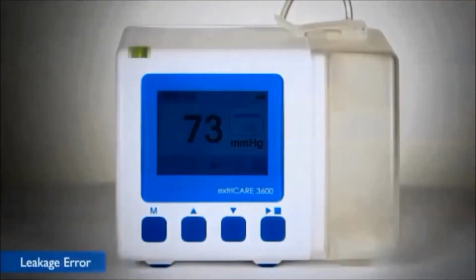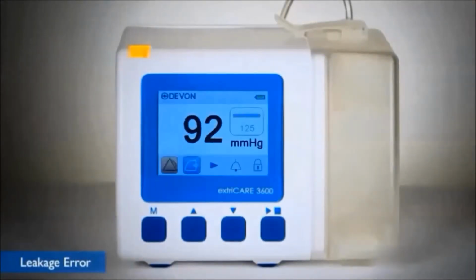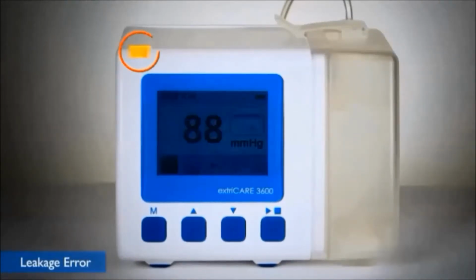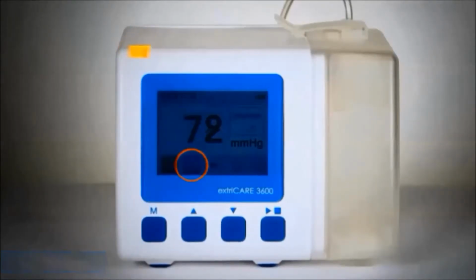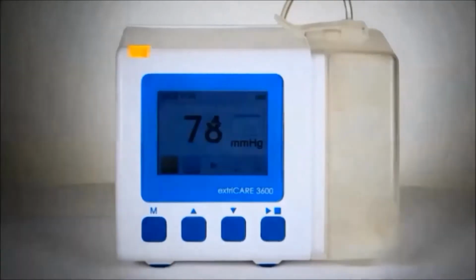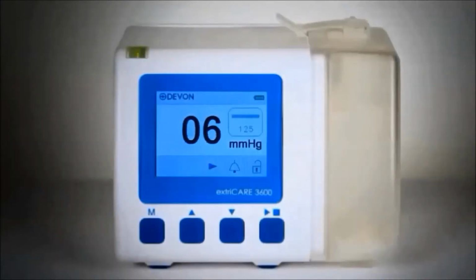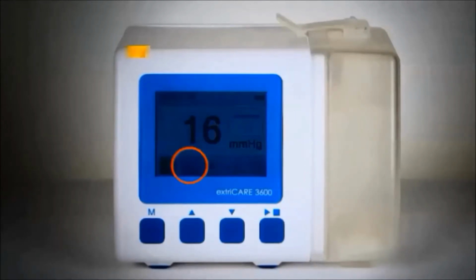The leakage error alarm will sound if the pump is unable to reach 80% of the preset pressure after 5 minutes. The yellow LED will stay on constantly and the minor leakage error symbol will appear on screen. The pump will stay on. If the pump is unable to reach 50% of the preset pressure after 2 minutes of effort, the alarm will sound. The yellow LED will flash and the major leakage error symbol will appear on screen. The pump will remain on, but will power off after 10 minutes of continuous alarm.